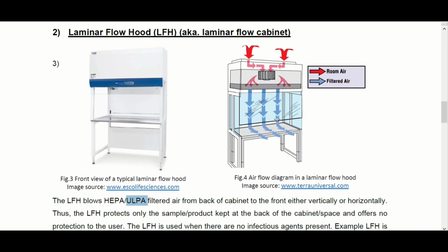That's why we can use it for biological testing, because in biological testing, such as microbiological testing, we need to ensure the area is clean, is free of contamination. So therefore, a laminar flow hood is suitable for biological experiments that are of low risk.